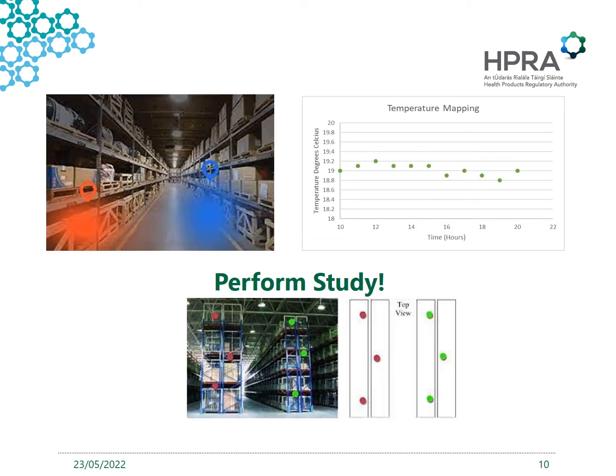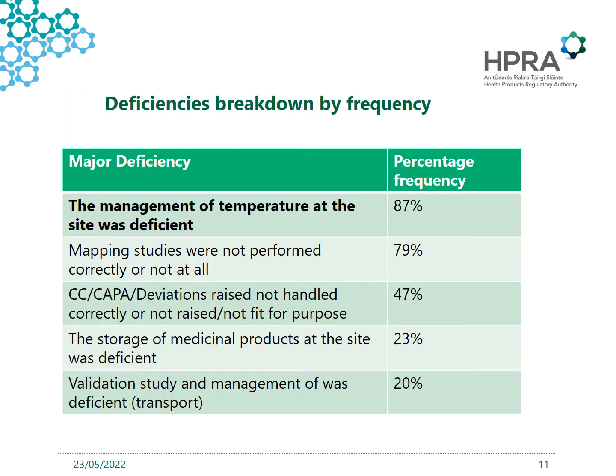After all the above is in place, the next step is to perform your study. At this point, I think it would be useful to check in with the deficiencies previously referenced. We saw the management of temperature at the site was deficient in 87% of the major deficiencies cited with respect to Chapter 3. Examples of that could include a failure to conduct an installation qualification or to document it, or a failure to conduct the study, the protocol, under normal operating conditions. We could see that there was no door opening study performed or no justification for the frequency of the door opening, that there was no power outage study performed, that it was not clear if equipment was in use during the mapping study, or that the risk assessment was inaccurate in that it failed to consider the risk of, for example, the proximity of the storage area to a window, a door, etc.